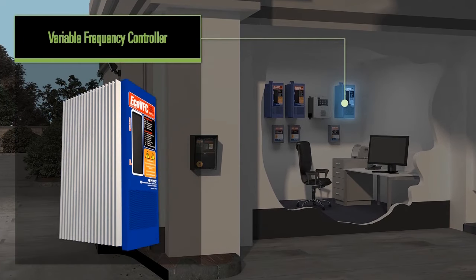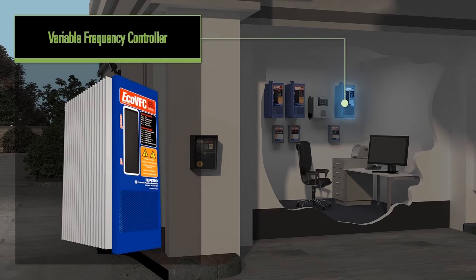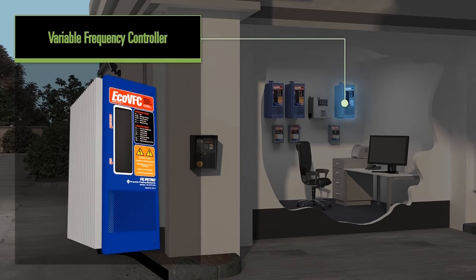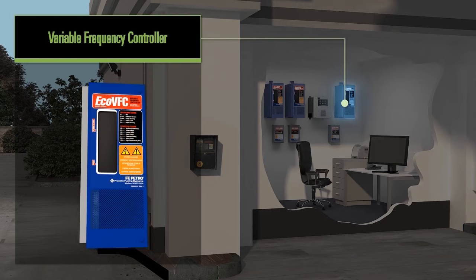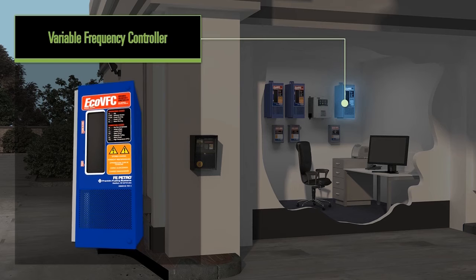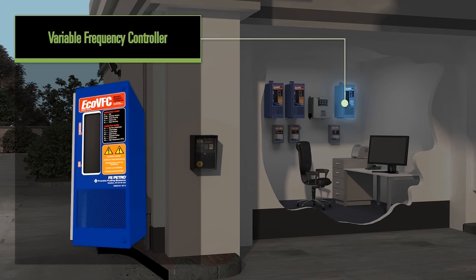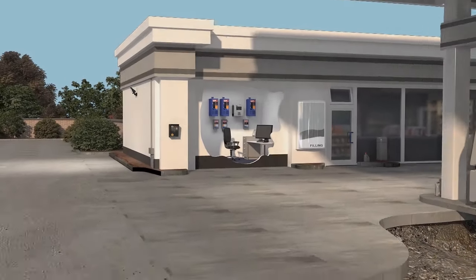For every submersible pump, there are controllers that communicate with the dispenser to initiate power when it is time to move fuel. In the case of variable speed pumps, the controller also varies the impeller speed to provide consistent fueling equally during busy and slower fueling times. The variable speed controller can also communicate the pump status to run the station as efficiently as possible.